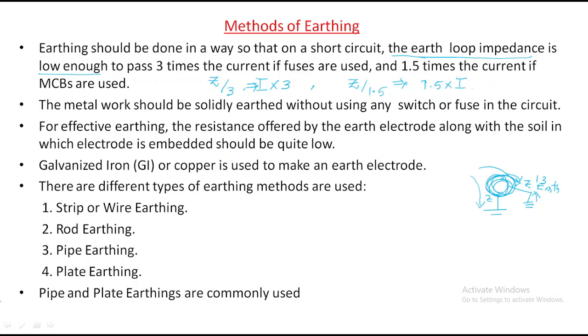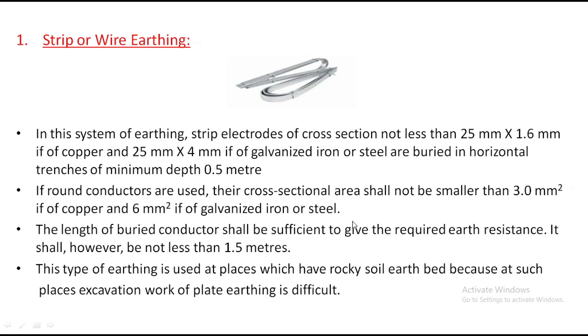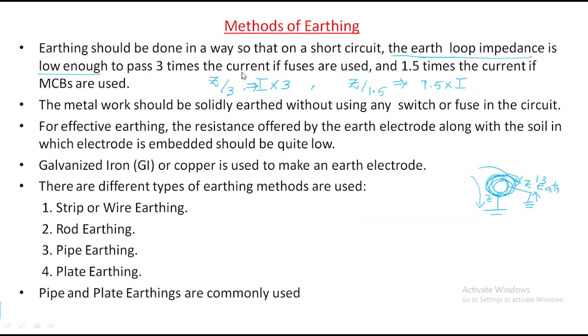Next, the metalwork should be solidly earthed without using any switch or fuse in the circuit. We don't use any switch or fuse. It is directly connected to ground. For effective earthing, the resistance offered by the earth electrode along with the soil in which the electrode is embedded should be quite low. Earth electrode means the point where we are connected to ground. That earth electrode resistance will be low.